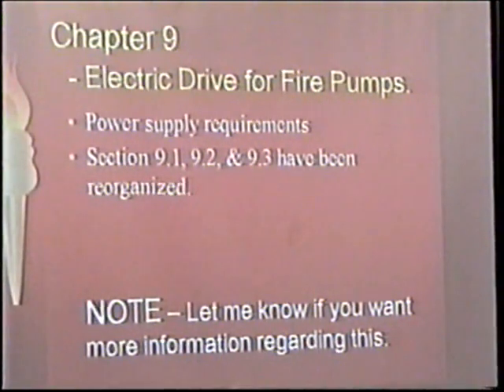Where we're going to have issues, and continue to have issues, I think, is for the high-rise buildings that have indoor substations in the building, and we're taking separate feeds off of that. There's a section in there now that says that the fire pump disconnect shall be isolated from other disconnects. So that means it probably should never come into that room. And that's going to be problems for building people, for the electrical contractors. If this isn't coordinated right on the front end, there's going to be issues when you get there and you go, well, wait a minute, this isn't per code, that's not per code. You know, what do we do?